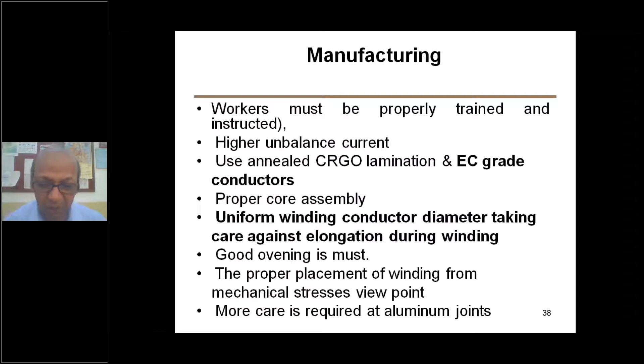More care is required at aluminum joints. This is very important. I have told you in the earlier slide that you have changed house wiring from aluminum to copper. Why have you changed? Only because of joints. No other problem. Termination and joints. If termination and joints could have been perfect with aluminum, no issue. You can use aluminum wiring in the house. But it is a very serious problem, and this is a serious problem for LT termination. When LT termination is there, and you don't have a spring action, you don't use washers, then you are inviting a serious problem of contact resistance at the joints, at the termination of the LT winding, which is very important.